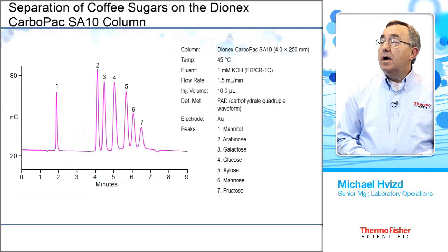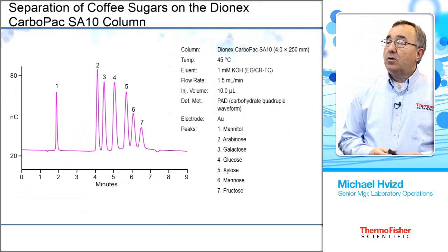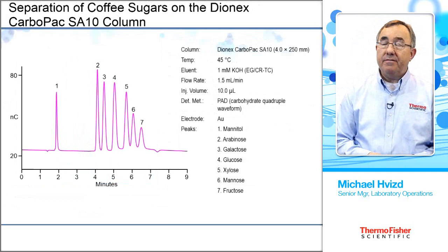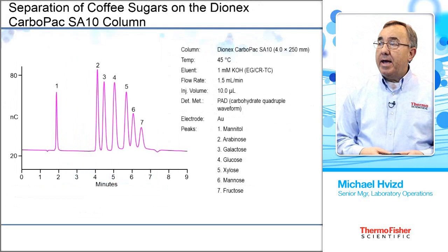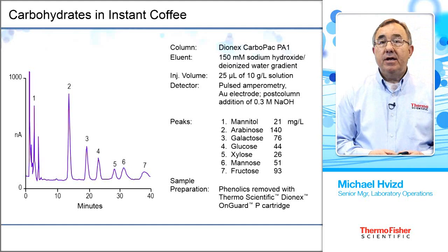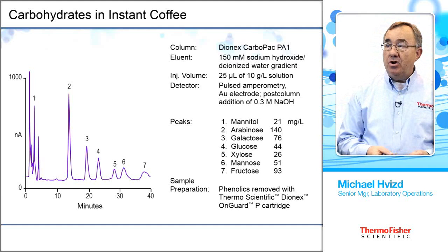The next separation shows a new method for coffee sugars. Coffee coming into the plant must be tested before it's sent out, so this analysis needs to be done with every batch from the production plant. Here we're showing about a seven-minute run on the Carbopac SA10 for sugars in coffee. The old method takes about 40 minutes for the same sugars, using a sodium hydroxide/water gradient — decreasing the hydroxide concentration over time to achieve separation. Compared to the newer separation, the old method is much, much longer.